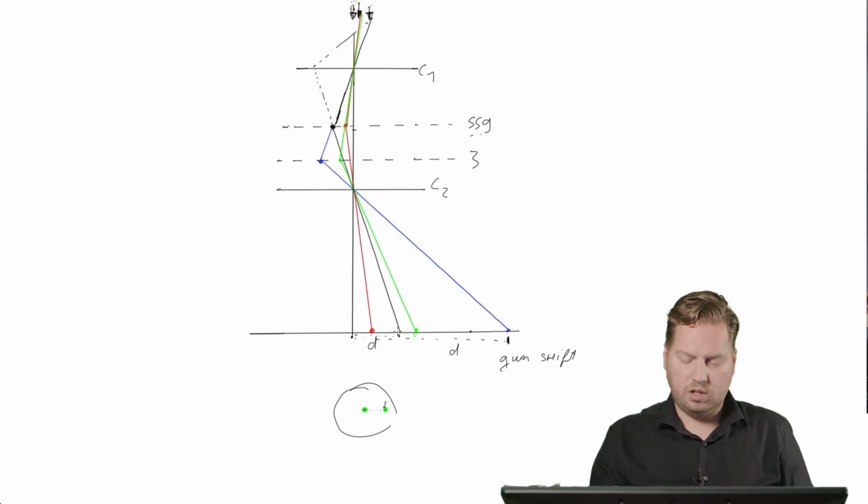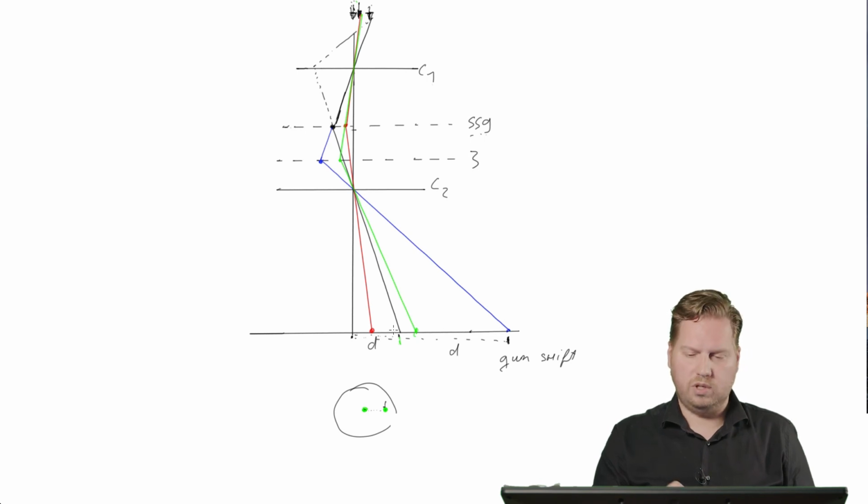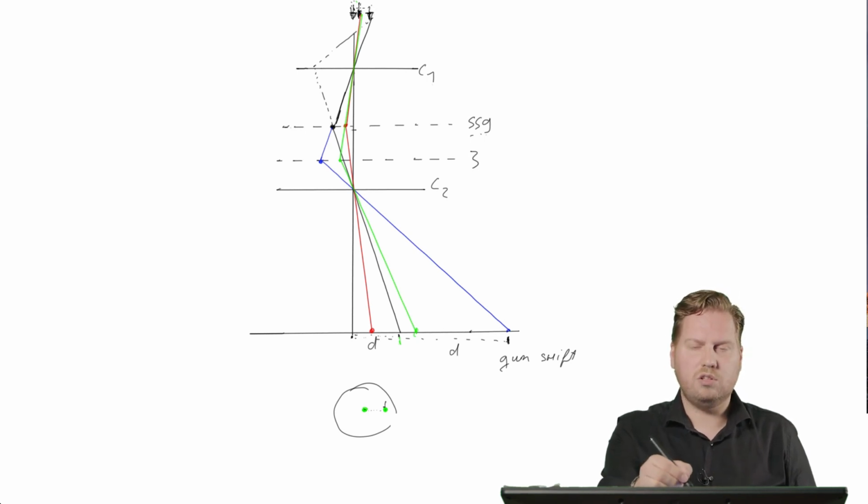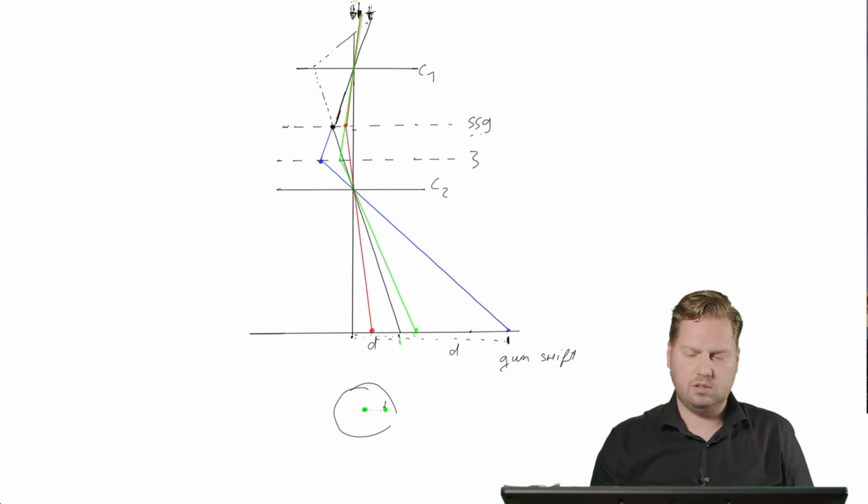The reason why you're not straight at the middle is because you start off with spot size 9 and your gun was shifted. So spot size 9 was not in the center. You only used beam shift to bring that spot to the center to more easily see where you have to go. So what you basically have done is you move spot size 9 to the position of spot size 3. That is not yet the center, but you have improved the situation. So the gun has shifted closer to the optical axis.